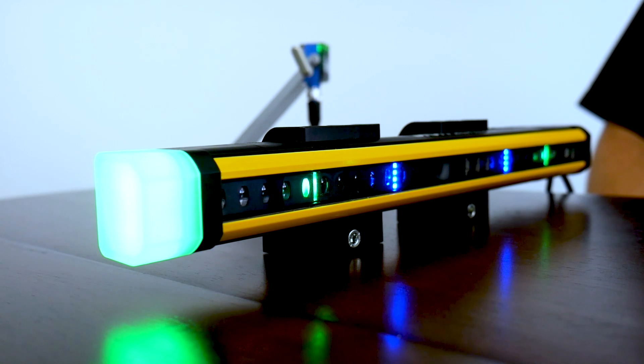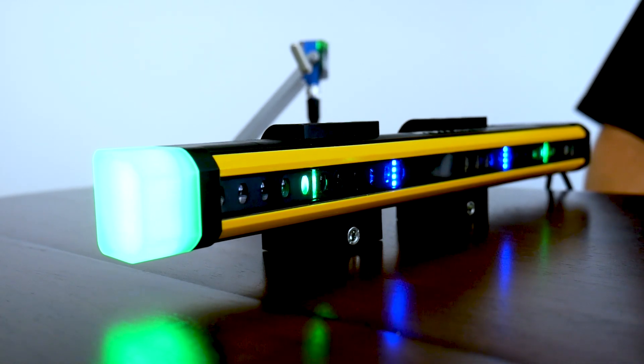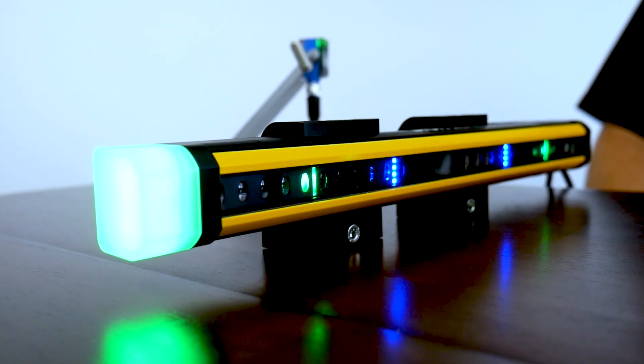As you can see, once it went into alignment, the four alignment LEDs on each bar lit up. The green indicator light went green, so that's good alignment. You can imagine when these things are separated by four or five feet — all the way up to five to ten meters — this might be a little tricky. That's where these flex fix brackets come in really handy, because they allow you to fine tune your alignment.